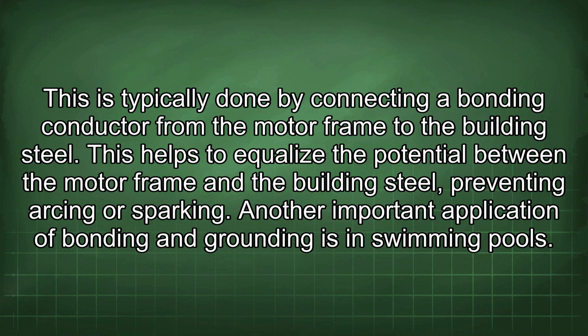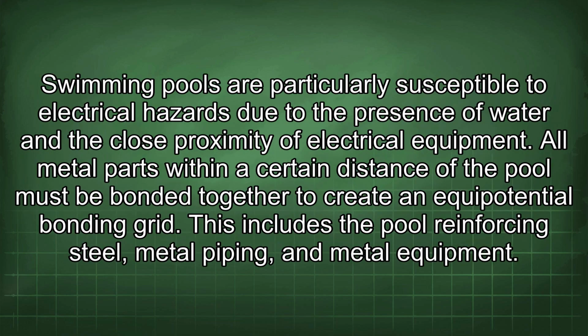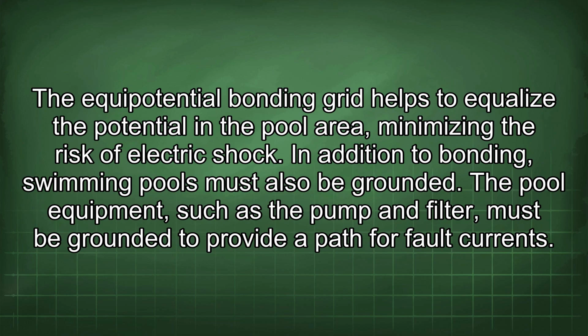Another important application of bonding and grounding is in swimming pools. Swimming pools are particularly susceptible to electrical hazards due to the presence of water and the close proximity of electrical equipment. All metal parts within a certain distance of the pool must be bonded together to create an equipotential bonding grid. This includes the pool reinforcing steel, metal piping, and metal equipment. The equipotential bonding grid helps to equalize the potential in the pool area, minimizing the risk of electric shock.